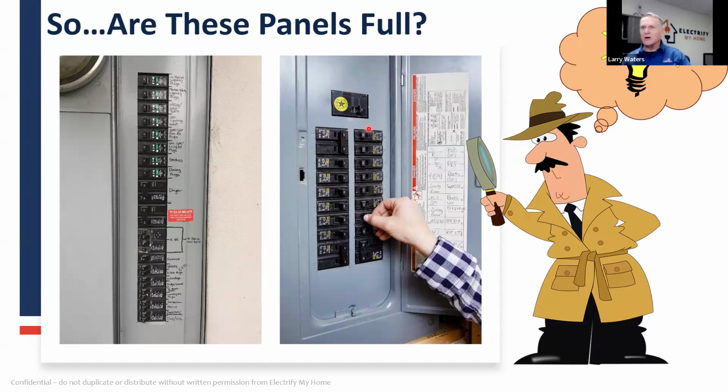125. All right, I've been saying it wrong the whole time. So, a 125 amp panel, lots of power on there. I've got a couple of 220 volt breakers, one here and one here, depending on what those loads are. And then I've got a bunch of larger breakers here, and these breakers can easily be removed and we put in a quad breaker or something. So we'll get to them in a second.